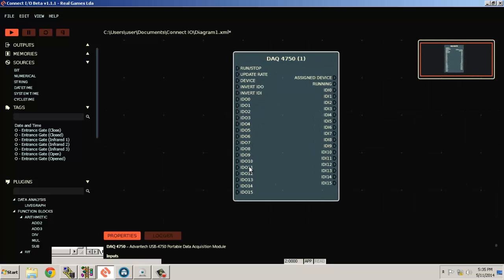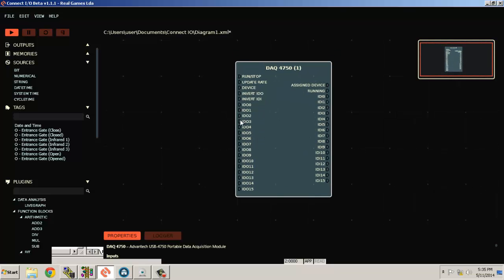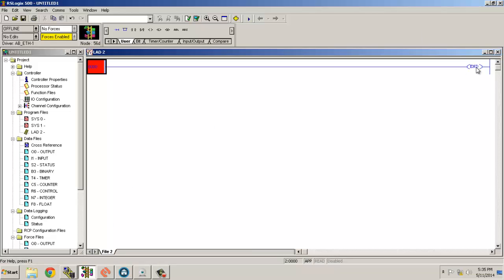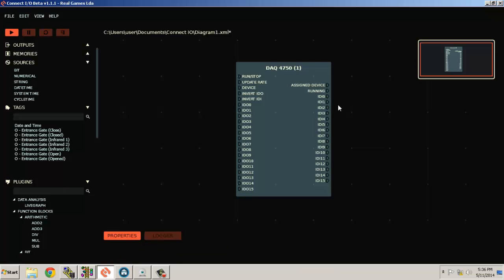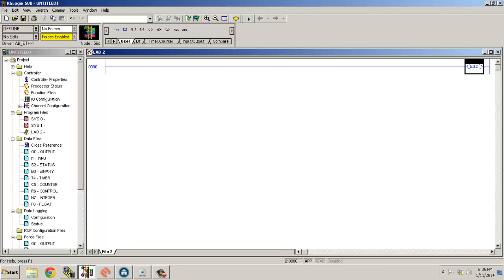Here it says IDO0 to IDO15 — these are the outputs of that card. The thing you need to understand is: the output of the PLC, which will be ON in the Allen Bradley software, will be reflected in the input of that card, because the output wiring of the PLC is going to the input. And the signal we give to the output of the DAQ card will go to the input of the PLC.